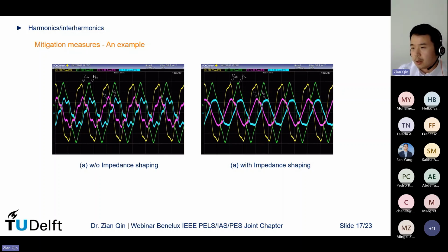As I mentioned, if there's harmonic or interharmonic issues, it's because of the mismatching between the two impedances, the charger impedance and the grid impedance. Again, grid impedance is not something you can easily change. I mean, it's time variant, but that is what it is—you cannot really change the grid impedance easily. But what you can do is change the charger impedance.